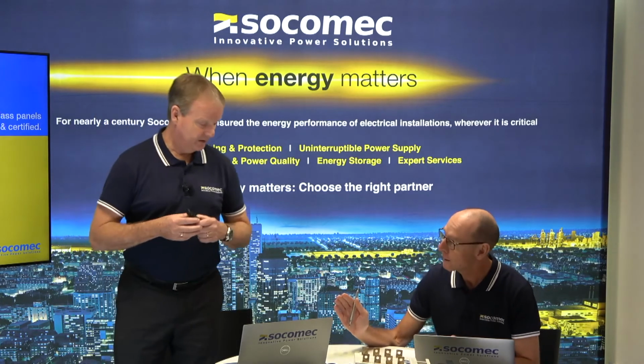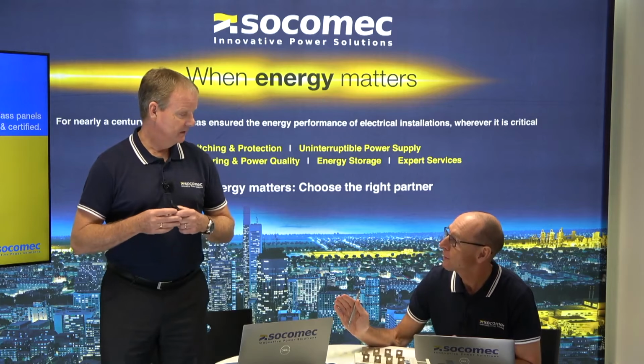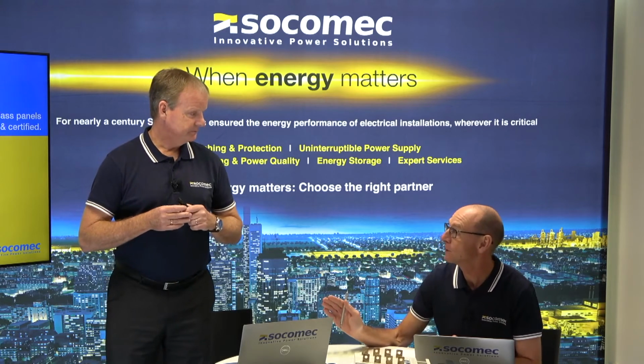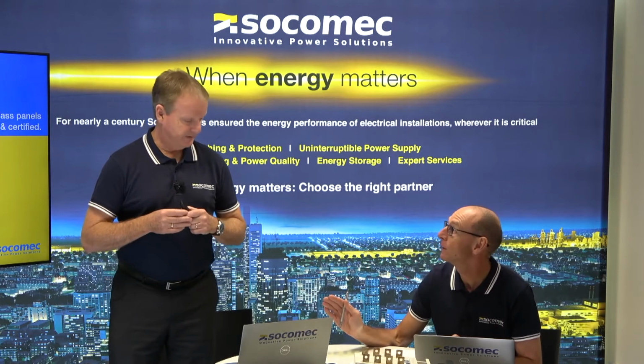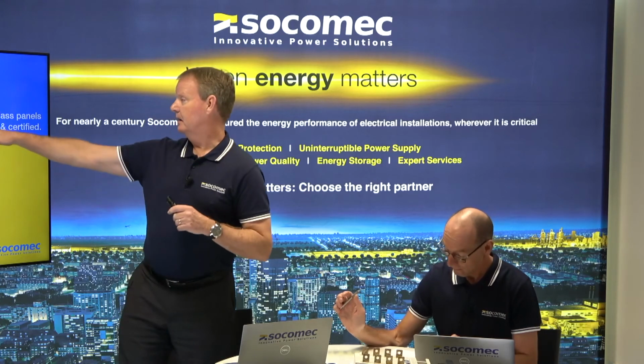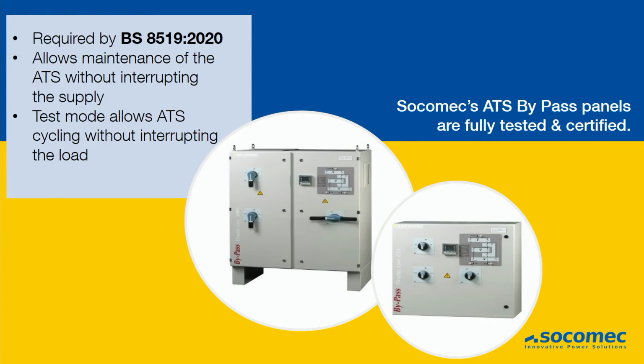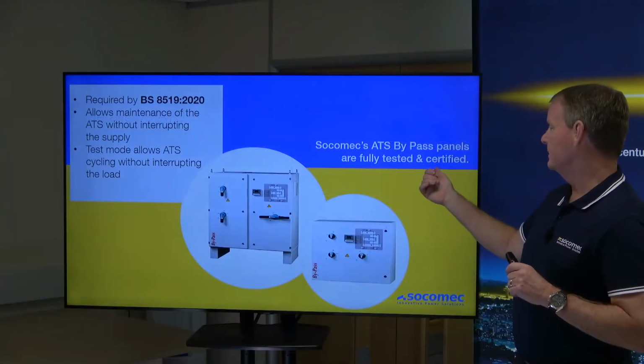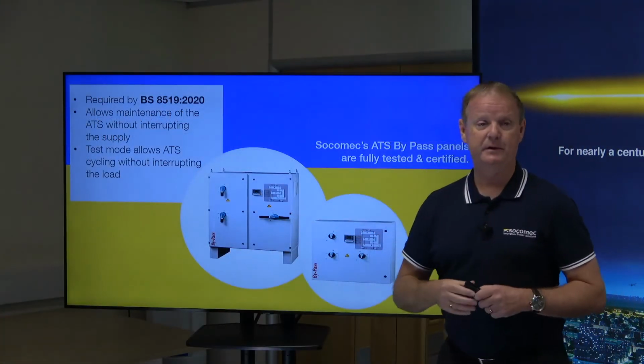That's exactly right. And I think the other key point is that the panel has to meet the low voltage specification 61439. Yes, that's correct. Yes, so it has to be tested, and as we've said, obviously Socomec ATS bypass panels are fully tested and certified. They can be put together by other people, but it has to be fully tested and certified using a transfer switch that complies to the standard.